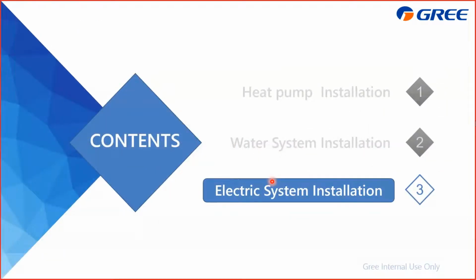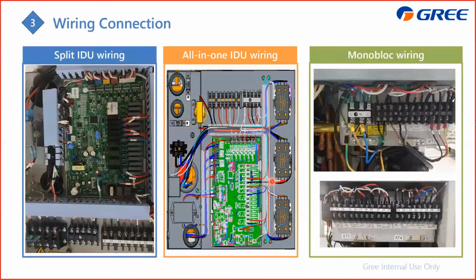And the last part is the electrical system installation. For this, you can find it here. It basically shows how to do the wiring for the split type, which is the indoor unit, and also the all-in-one indoor unit. As for the monoblock, it is all in the outdoor unit. So this is the wiring diagram. Here is where to do the wiring for the split indoor unit, and for the all-in-one it is on this part.